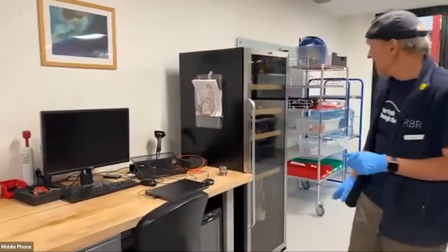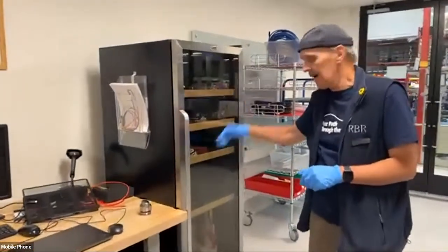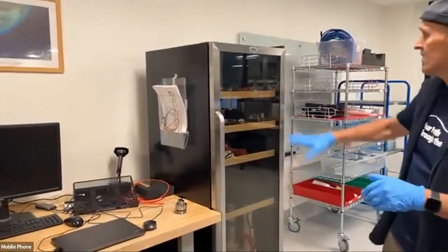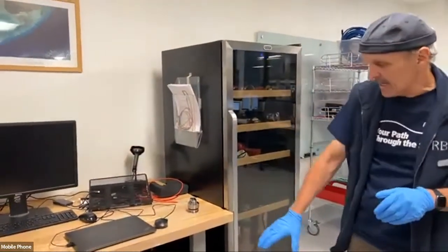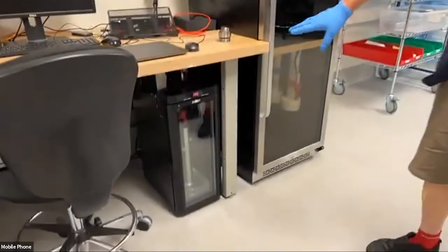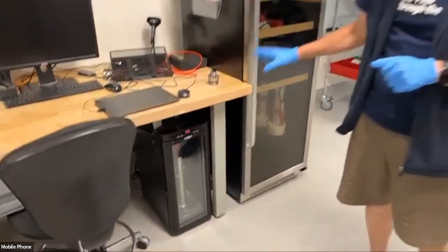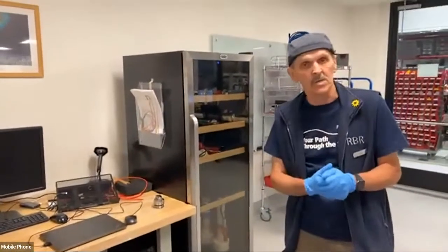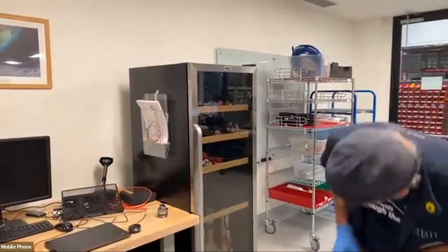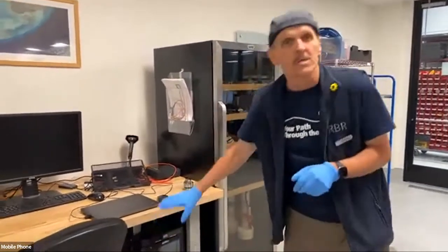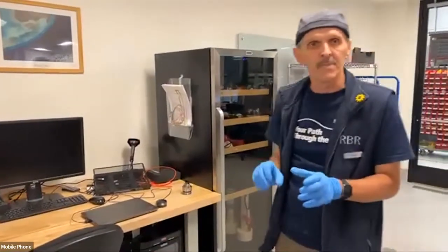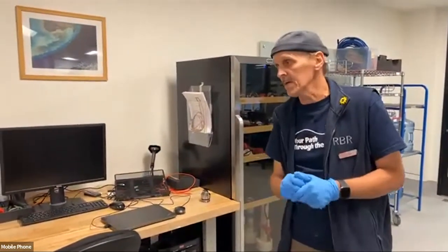So you can see the climatizing cabinet, which is set again to 15 degrees, and another chamber where we set 15 degrees temperature. When we run what's called a resistance test, there's a device called a resistance box. We set up a very precisely and accurately measured resistance.